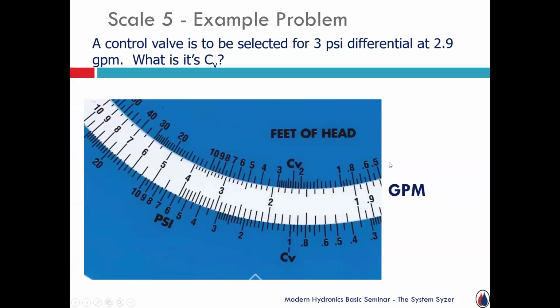So I could do the math, or I could just grab scale 5 real quickly on my iPad or my plastic wheel, and I'll say, hey, what do I know? What am I chasing after? I want a 3 pound pressure drop at a flow rate of what? 2.9 gallons a minute, right? So there's my 3 PSI here. The bottom side of that scale 5 is in PSI. So 3 PSI, which is what I'm chasing. My flow rate, I said, was established to be 2.9 gallons a minute. So 2 gallons a minute, 3 gallons a minute, 10th increments. So 2.9, line those two.